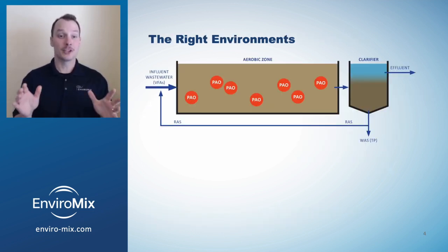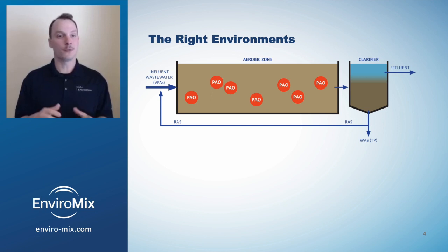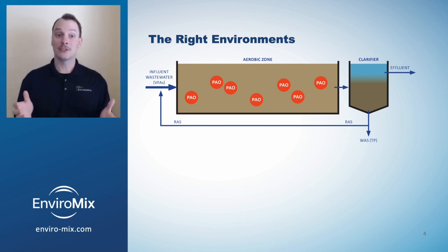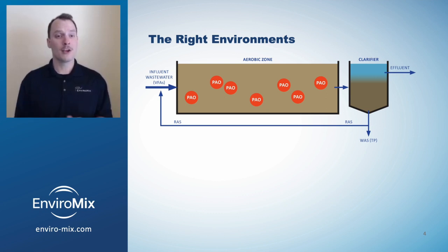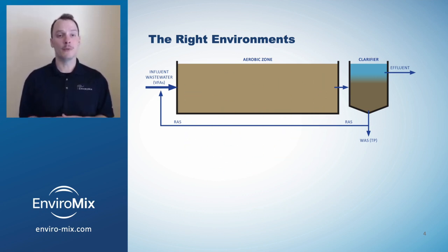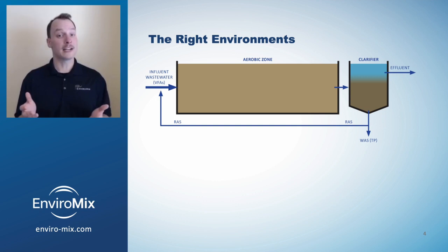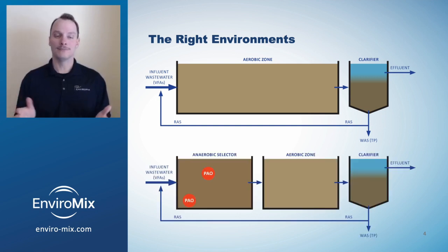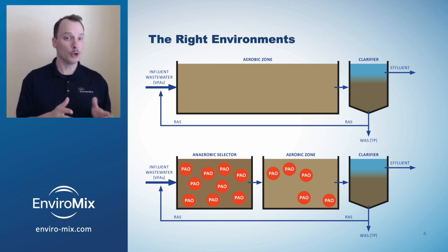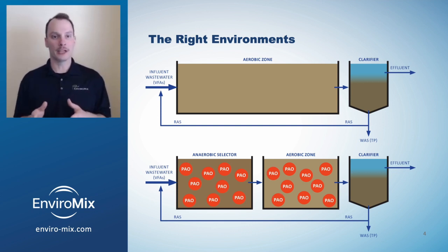Activated sludge is a community of microbes that are all vying to thrive in a competitive environment. In activated sludge processes with aerobic and anoxic environments, PAOs are unable to compete with other microbes to access the food. However, when the activated sludge is exposed to alternating anaerobic and aerobic environments, the PAOs are selected and able to flourish.